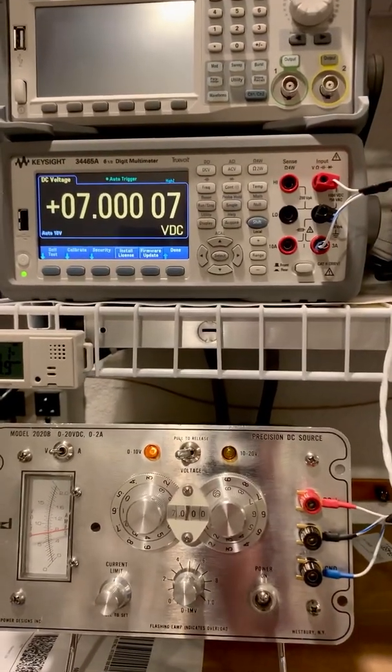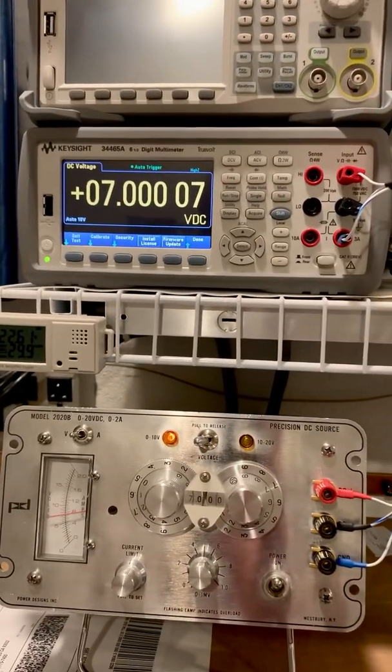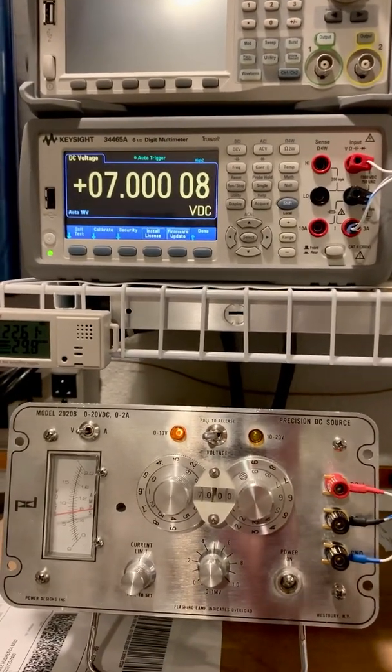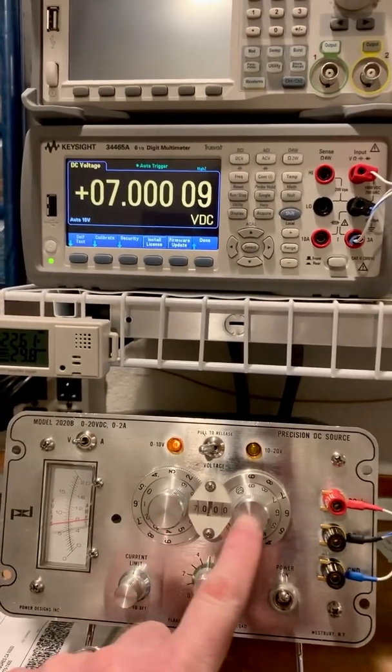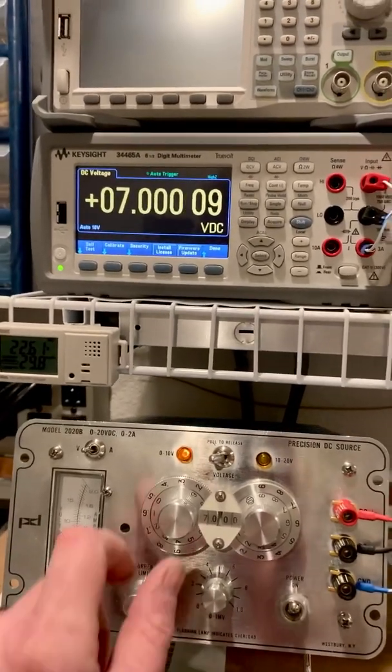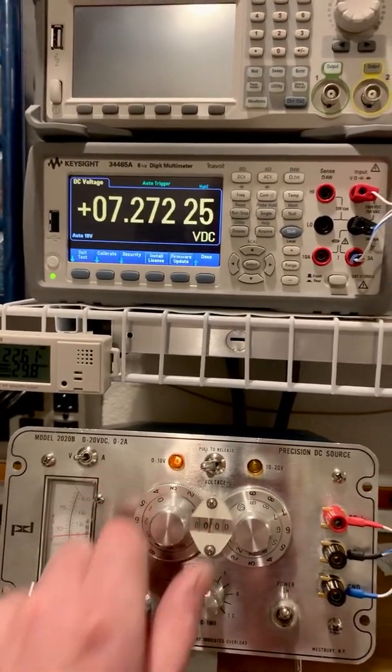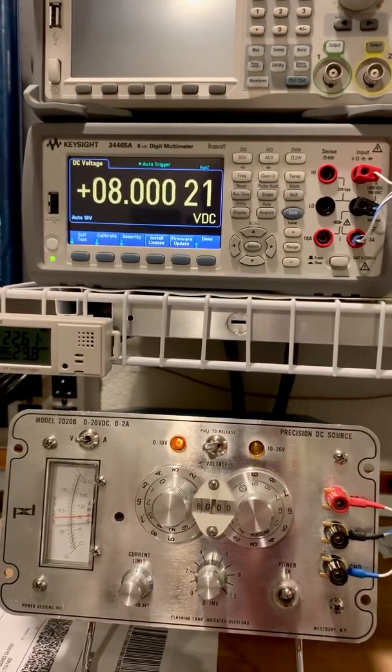Using some high value resistors I had, I was able to put them in parallel across the 200 ohm and 2k ohm resistors used on the decades and bring them back down to almost exactly where they should be. Everything tracks and sets well within spec.